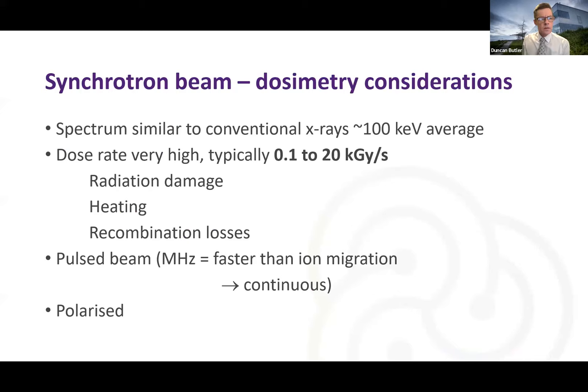So some considerations for dosimetry. We've already seen the spectrum. It's similar to kV x-rays, around 100 kV average. The dose rate is very high, typically between 0.1 and 20,000 gray per second. So that means you get radiation damage. In fact, any detector with too much plastic in it can suffer damage. Some ion chambers only last a year. Also you can heat the chamber up. If you're measuring an ionization chamber repeatedly, it will get hotter and the signal will go down. And the big problem is recombination losses because these are very high dose rate. The beam is pulsed. The electrons are pulsed and so the photons are pulsed as well. However, it's extremely fast, faster than ions migrate inside ion chambers or inside the air. So the beam can be considered continuous. And as I mentioned before, it's polarized.